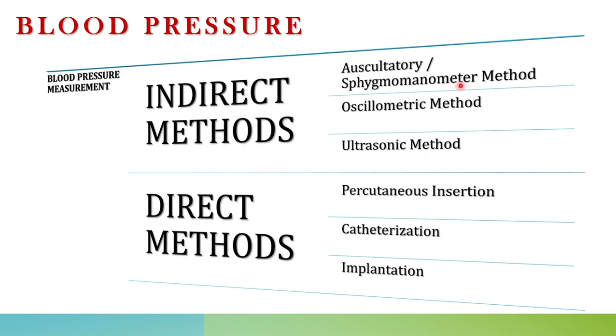In the last class we covered the auscultatory or sphygmomanometer method, where we use a sphygmomanometer along with a stethoscope. Based on the variation of the cuff pressure, we read the sounds in the stethoscope and take readings on the manometer to find the systolic and diastolic pressure. The second method is the oscillometric method, where based on cuff pressure variation we measure the oscillations happening in the blood vessels.